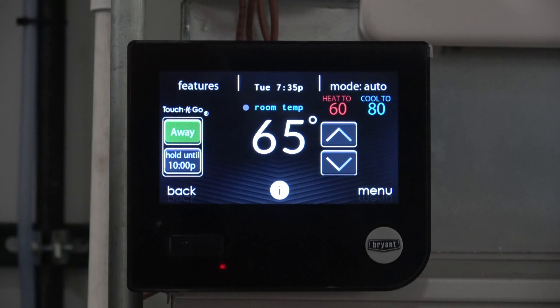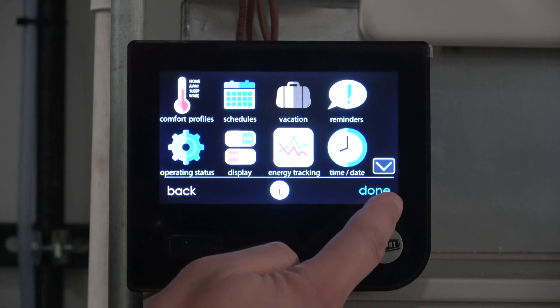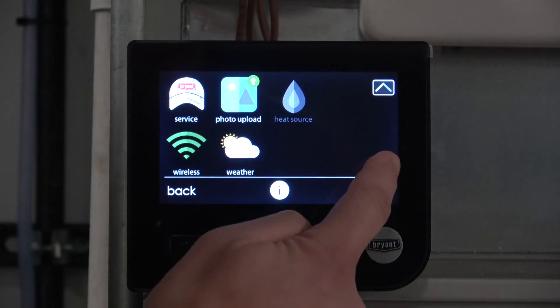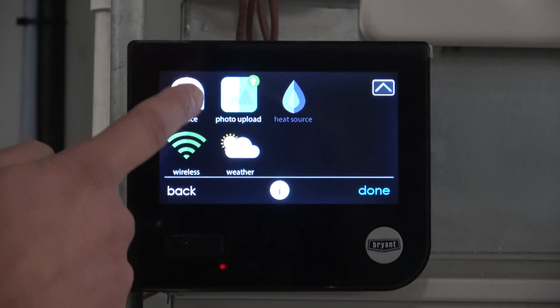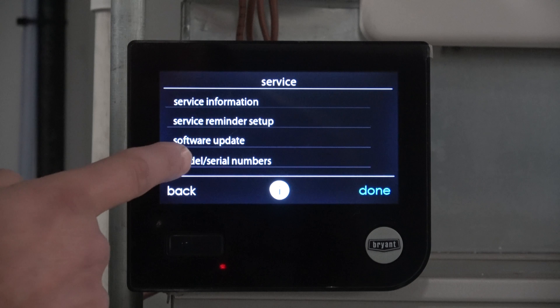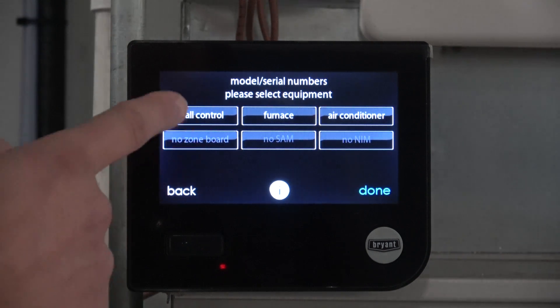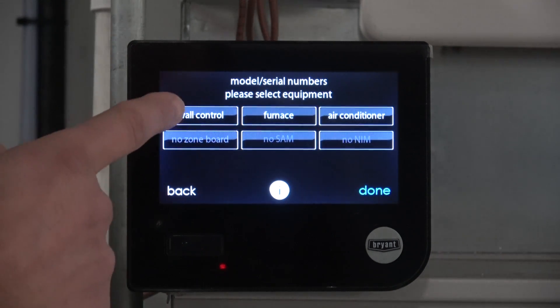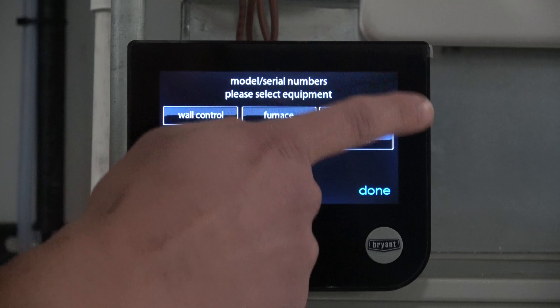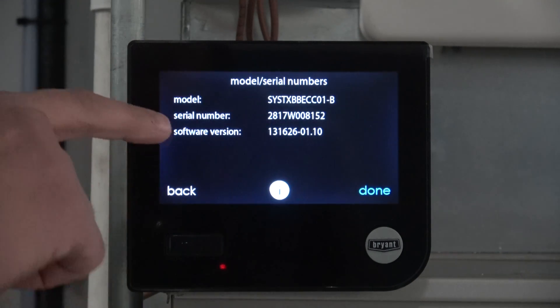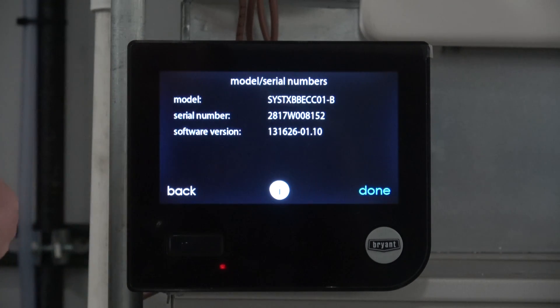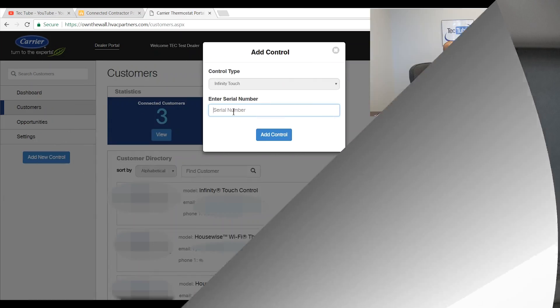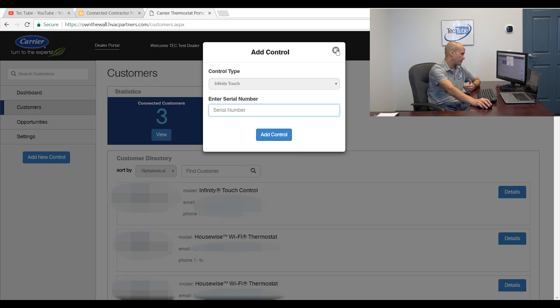On the Evolution Connex or the infinity touch, we'll go to menu. We'll scroll down to service. Models slash serial numbers. In this case, we want to get the model and serial number from the wall control, not from the furnace or the air conditioner. So I picked the wall control and there's my serial number right there, 28, 17, etc. So I would have put that serial number in here and I would have added that stat if I wanted to add that stat on.